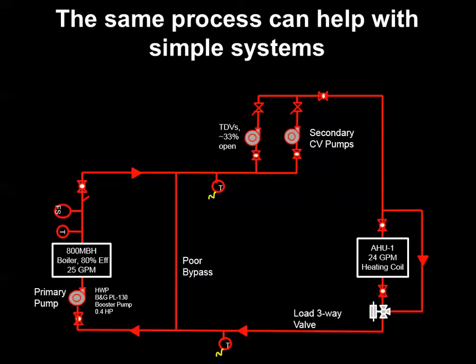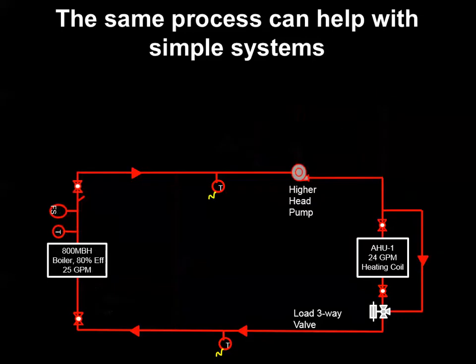However, even in simpler setups, the system diagram can be a valuable tool. Take this basic primary-secondary system. Poor bypass and throttled distribution pumps were discovered, but using the system diagram, the RCx team was able to point out that based on supply temperature set points, the valve type at the load, and the GPM requirements for both the load and the plant, the system could not just be repaired, but improved to a more suitable primary-only configuration.